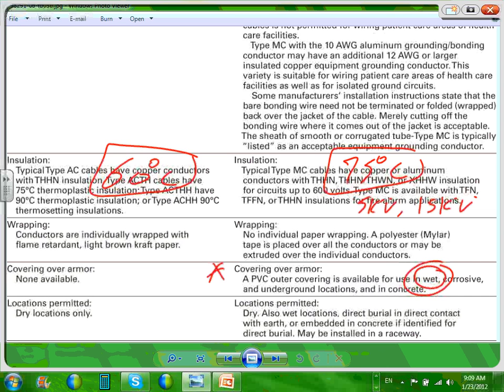So you have an air handling unit. Take this, an air handling unit on the roof. And you need to tie to this air handling unit on the roof, or rooftop units, from a disconnect. Your options are liquid tight flexible non-metallic conduit, or metallic conduit, or an MC cable with PVC jacket on it. They make them. So my point is, guys, it gives you a lot of options for location. And here's the disadvantage of this: dry location only. Look at that, dry.